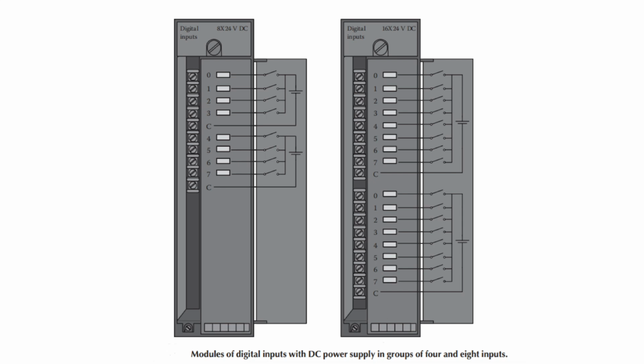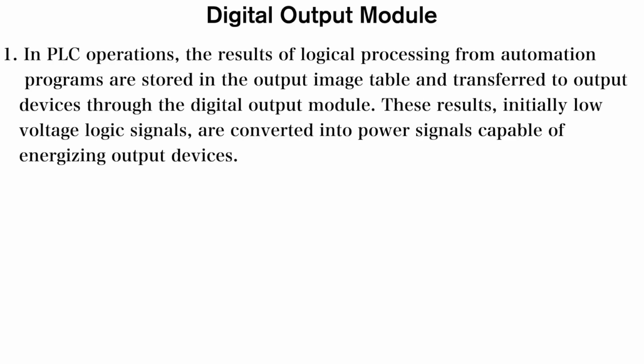Some programmable logic controllers group inputs into 2, 4, or 8 input sets with separate power supplies, as you can clearly see in the next figure. Next, the digital output module. In PLC operations, the results of logical processing from the automation programs are mainly stored in the output image table and are then transferred to the output devices through the digital output module.